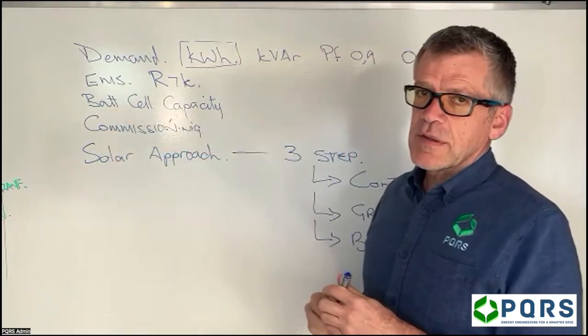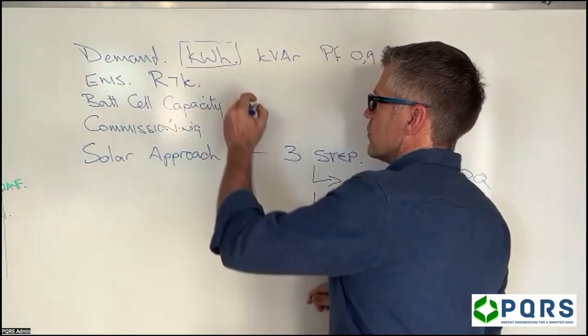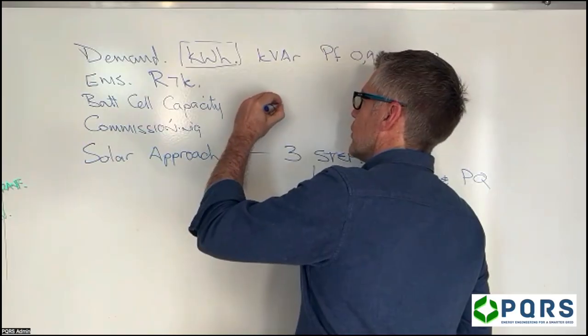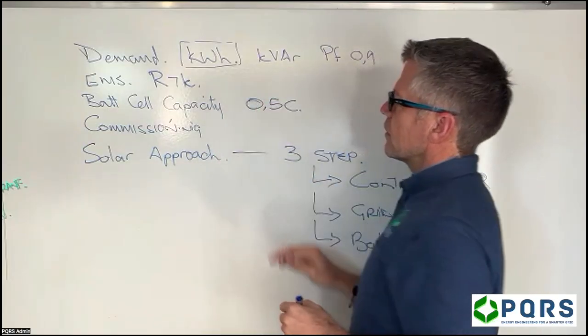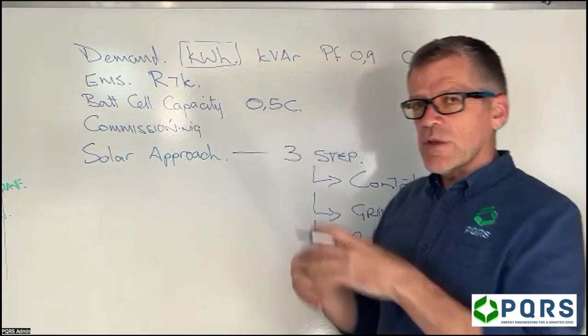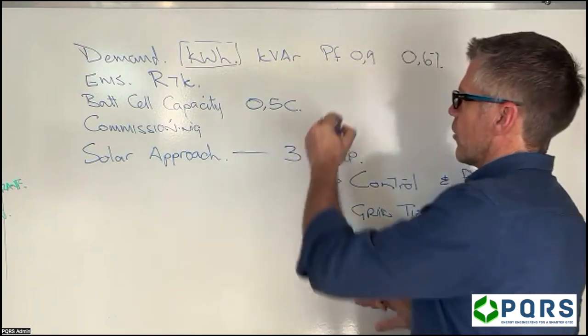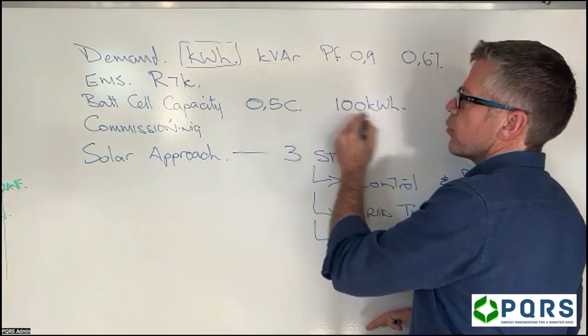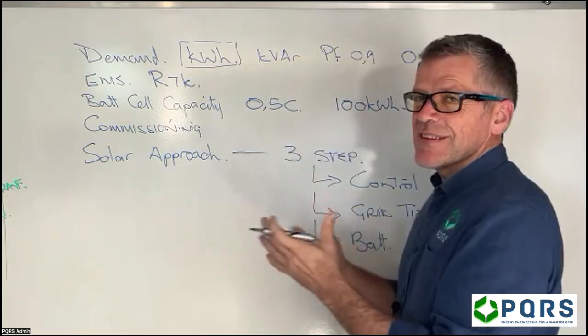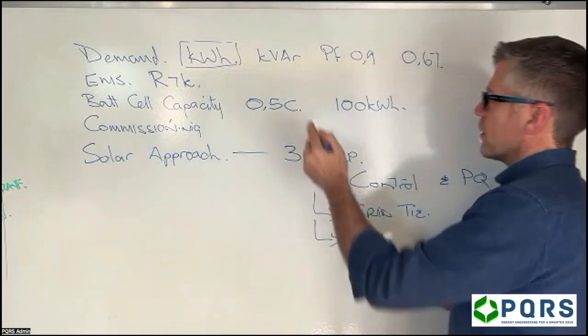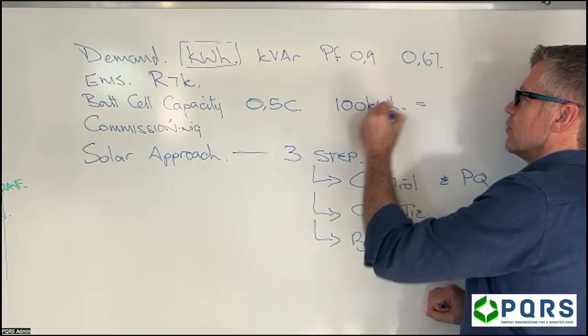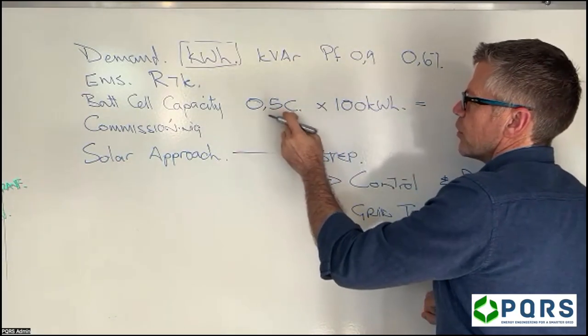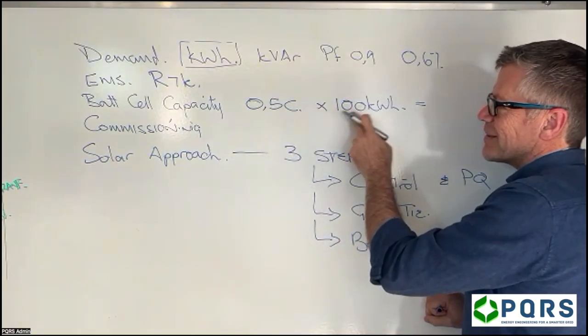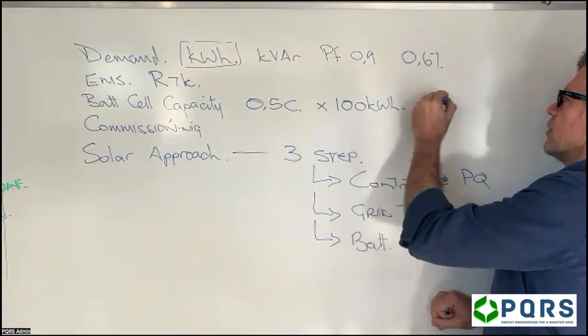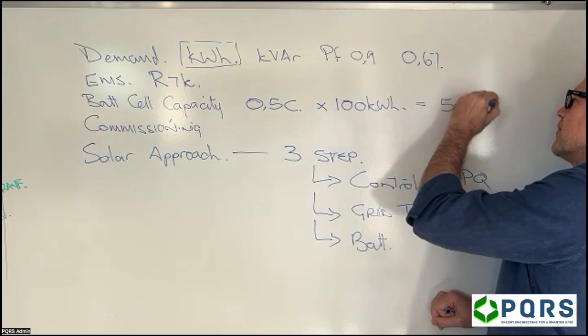Battery cell capacity: the batteries you've been quoted have a 0.5C rating. This means that for a 100 kilowatt hour battery pack with a 0.5C rating, the power you can draw out is 0.5 times the capacity, which equals 50 kilowatts.